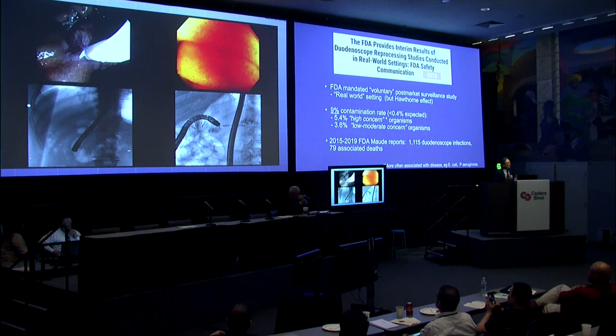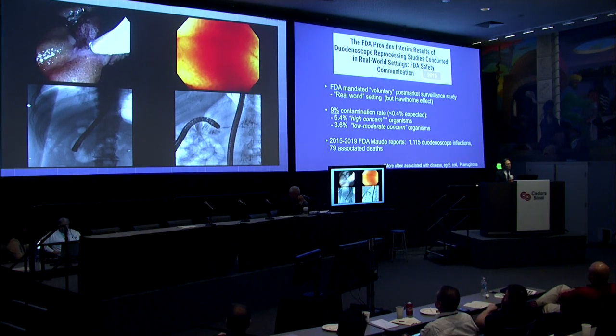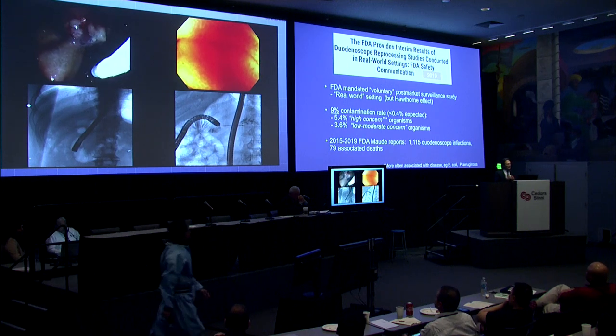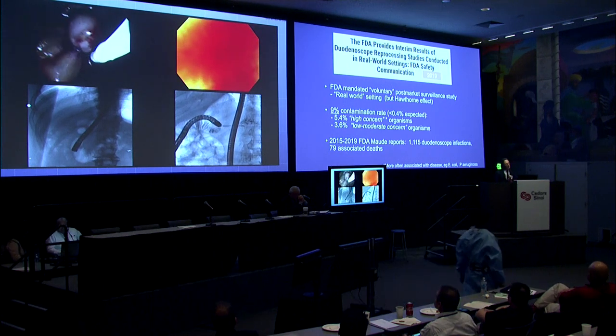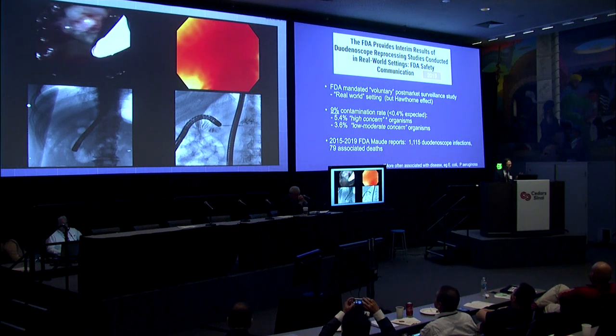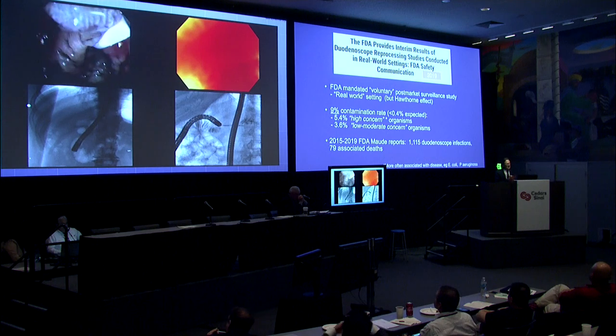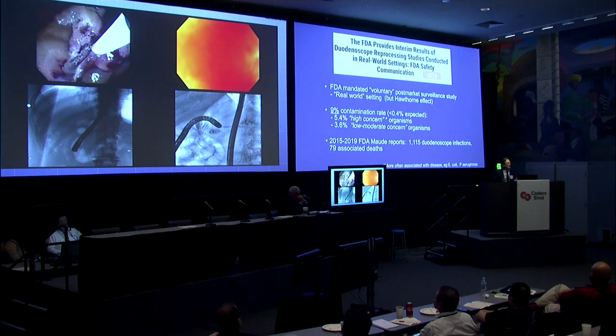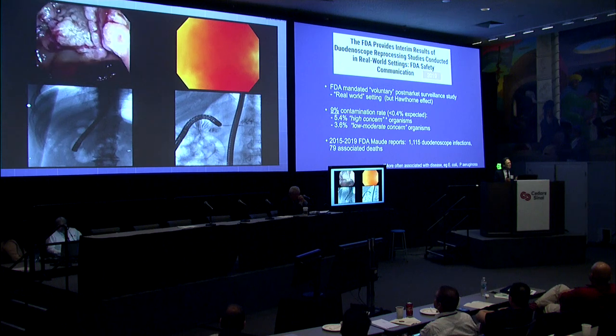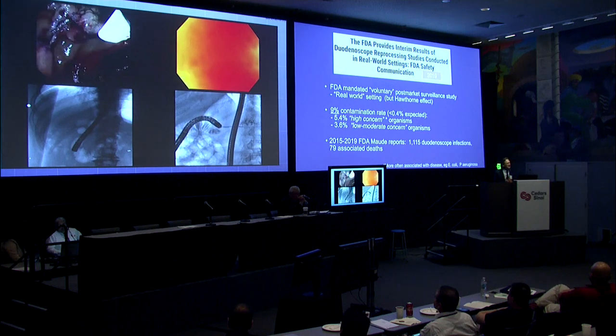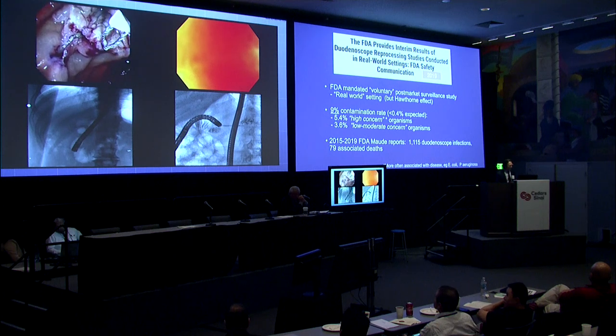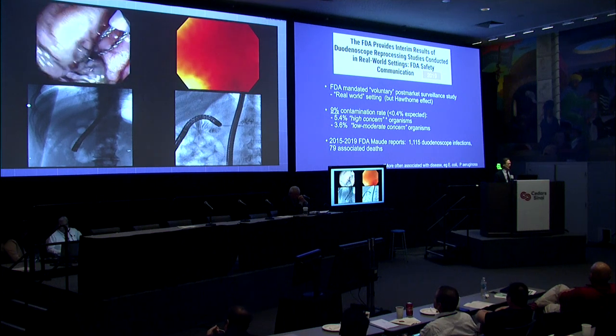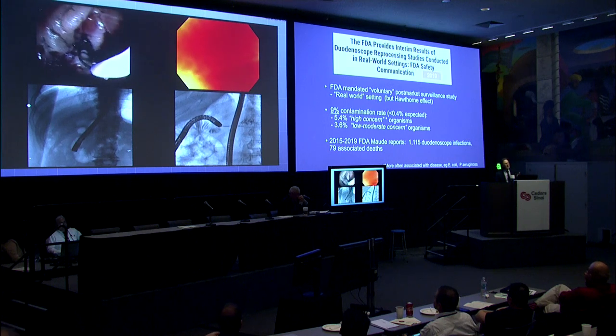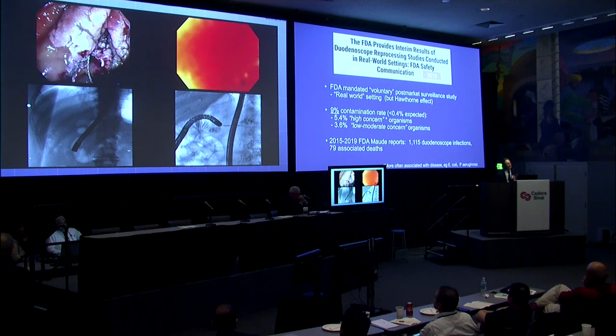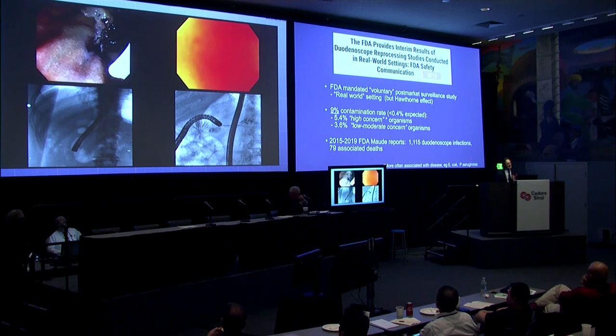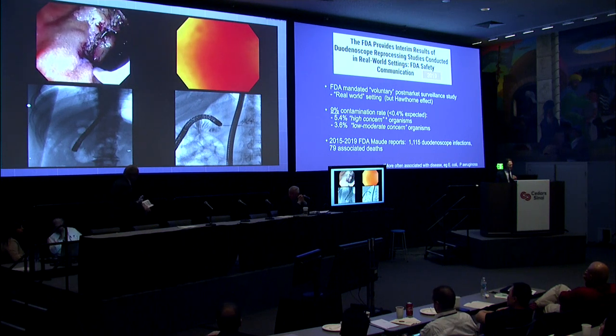And the FDA, of course, got wind of this. So back in 2013, they immediately mandated a voluntary post-market surveillance study in a real-world setting. The data took several years to collect, in part because the scope manufacturers were hesitating to actually collect this data, perhaps afraid of what it might show. And what it did show was a 9% contamination rate. The FDA was expecting a 0.4% contamination rate. So that's a significantly higher contamination rate.